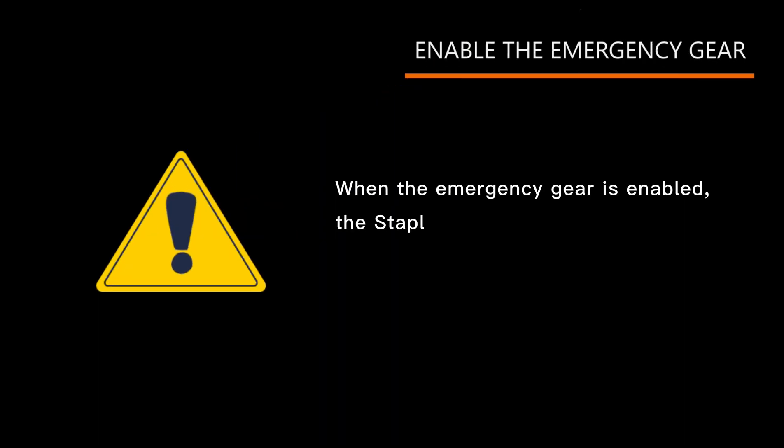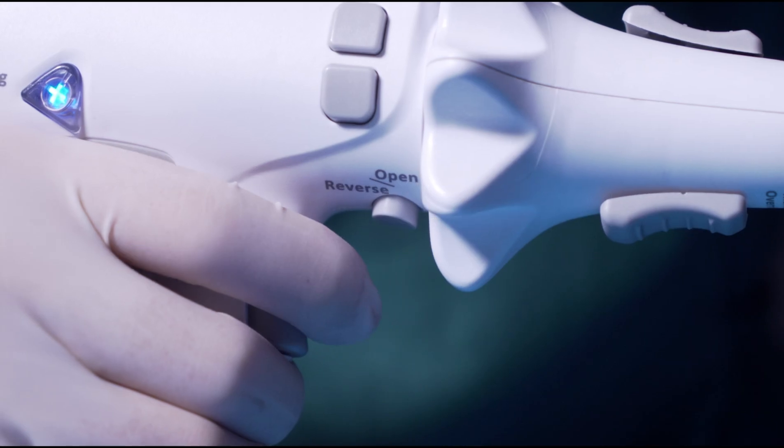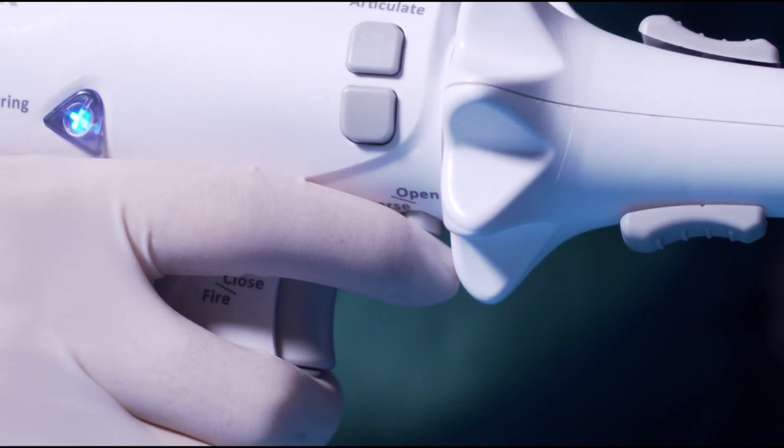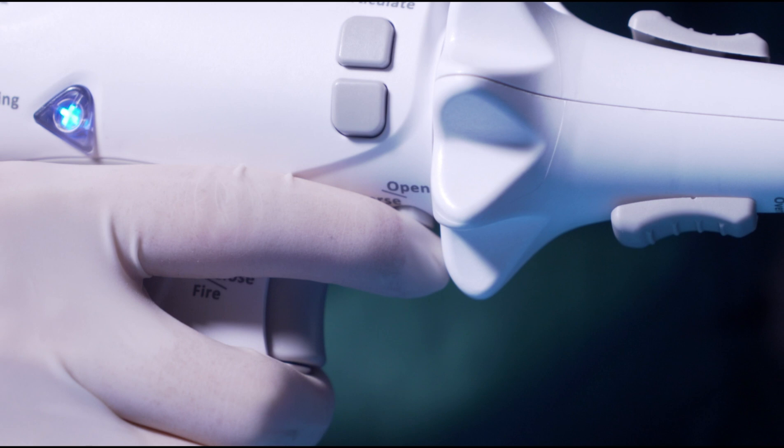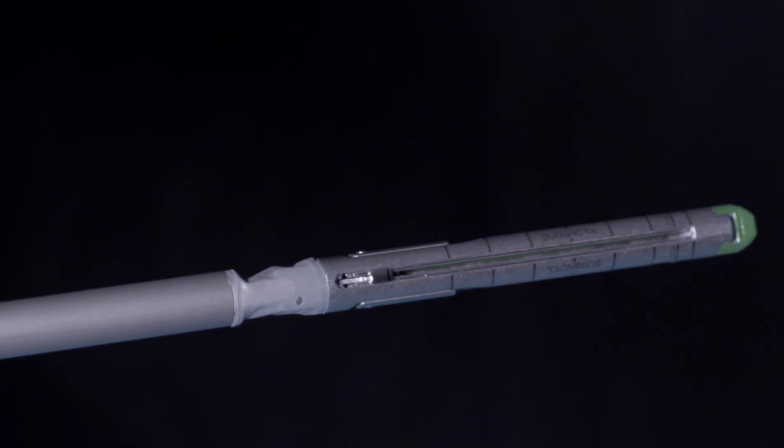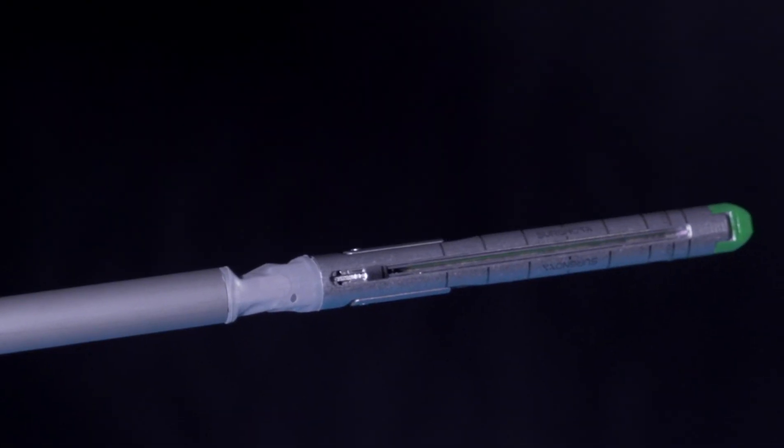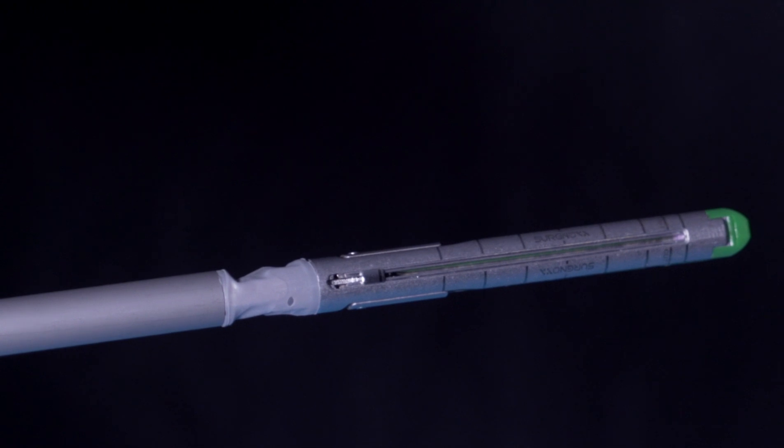When the emergency gear is enabled, the stapler will be in a disabled state and unable to be used for any subsequent firing. If the jaws are not open after pressing the reverse button, please first ensure that the battery pack is firmly installed in place.